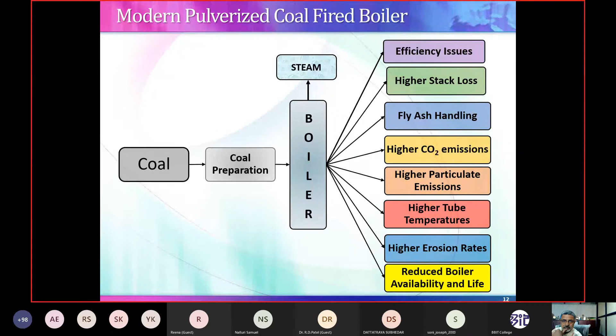So the first target is boiler efficiency for better energy management. The simplest formula which you have all learned is boiler efficiency is useful output by input. That is m dot s, the steam generation, into HS minus HFW, enthalpy of steam minus enthalpy of feed water, divided by m dot f, the fuel consumption, into GCV at constant pressure. I am writing this specifically because when we fire this coal, whatever calorific value you get is GCV at V equal to constant. But when we fire into the boiler, it is a constant pressure system. So you need to convert it into GCV at P equal to constant. So this is the basic formula.